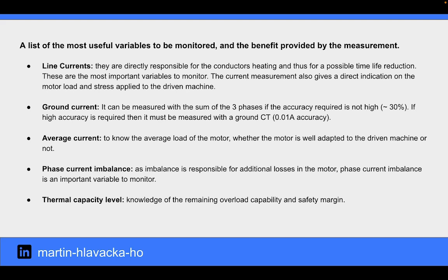Ground current. It can be measured with the sum of the three phases if the accuracy required is not high. If high accuracy is required, then it must be measured with a ground current transformer. Average current. To know the average load of the motor, whether the motor is well adapted to the driven machine or not.